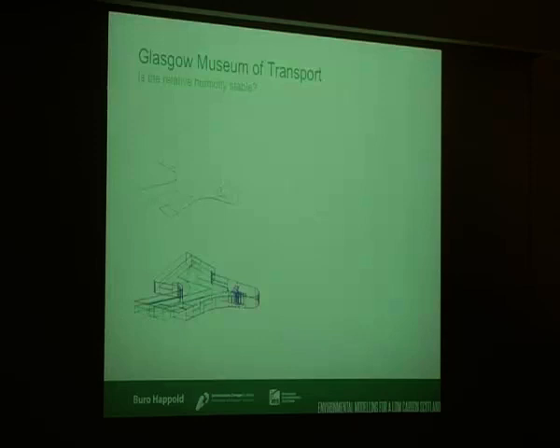What we did here was the question: is the relative humidity in such a large space going to be stable? What we did to determine that was to break up the volume both horizontally and vertically. Once we'd broken up the volume into different zones, we looked at an occupancy load profile - this is the one the client gave us. This was the worst case: if 1,500 people come in in the morning and don't leave until nighttime - that happened on the first day. So we're trying to determine what the risk to the client is in having that condition. That was some of the modelling we did in the Transport Museum.